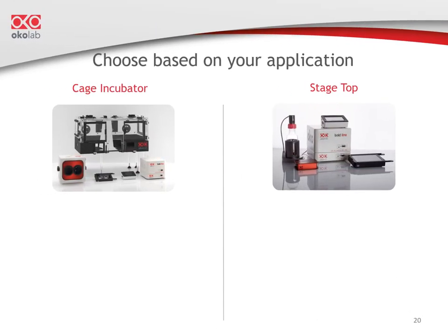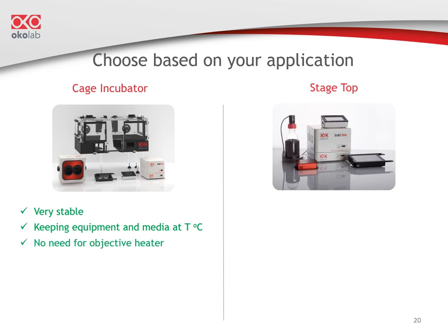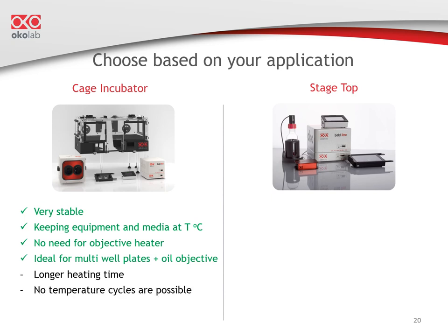When selecting your incubation system, think about your lab setup and application. A cage incubator is extremely stable — the enclosure protects your sample from drafts and room temperature fluctuations. If you're doing perfusion, you can place pumps, media, and other equipment inside the enclosure to equilibrate to 37 degrees. You never need an objective heater, so if you're mostly imaging multi-well plates with oil immersion objectives, a cage incubator is highly recommended. Note that it takes longer to heat up due to the enclosure volume, and you can never do temperature cycles.